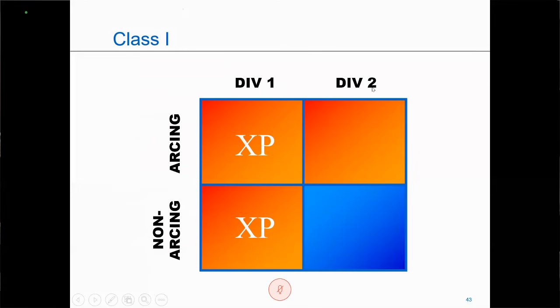Now, as I move over to Division 2, here my gases aren't normally present. But what if they become present and migrate into my motor starter? I could have an explosion with that one fault condition. So I need that explosion-proof equipment. Now, remaining in my Division 2 area with my terminal box, now I need to have two fault conditions. And really, these fault conditions need to be in the same time frame. An area where gas wouldn't normally become present would have to become present. An item that wouldn't normally arc would have to arc. And so because of that, in that particular application, the National Electrical Code says that my boxes and fittings are not required to be explosion proof.